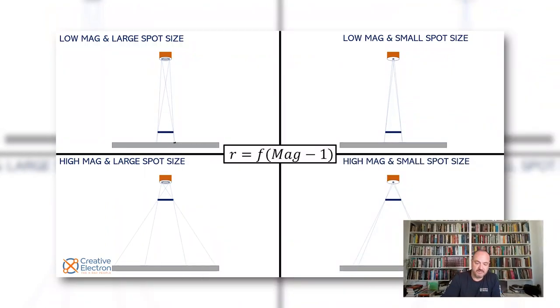Part one we talked about what happens when you have an ideal detector, and by ideal detector we meant a detector where the pixels are really really small, zero size pixels. So we end up with infinite number of pixels on an x-ray detector and we determine that the resolution in that case is equal to F which is the focal spot size on the x-ray source times magnification minus one.